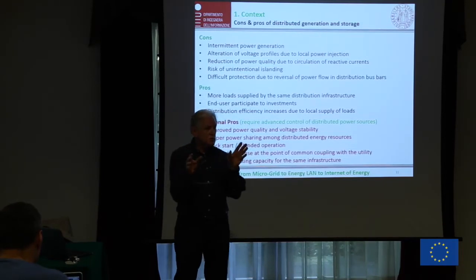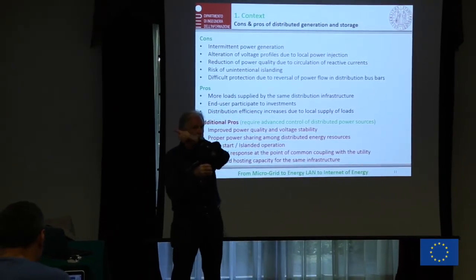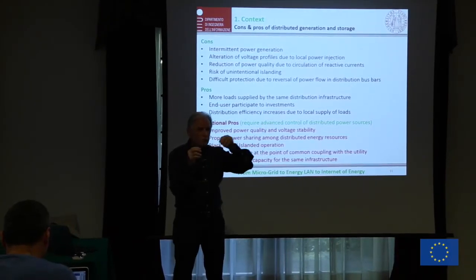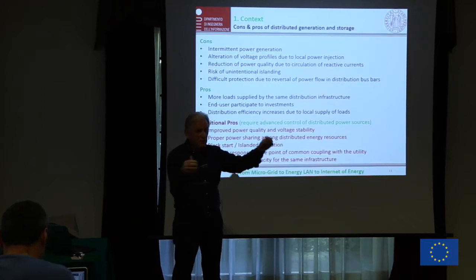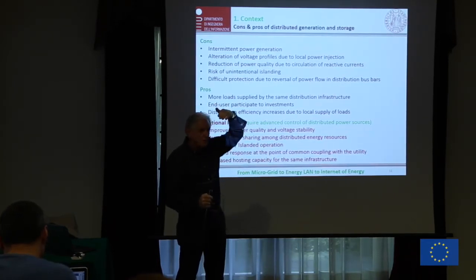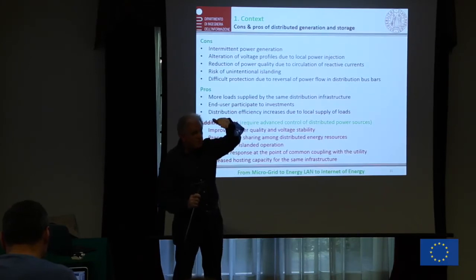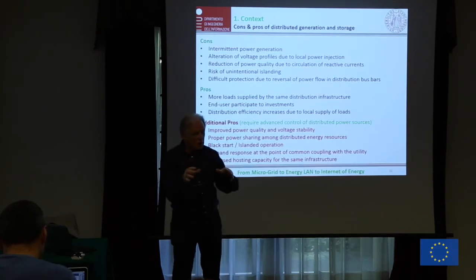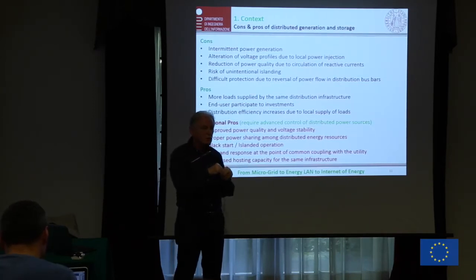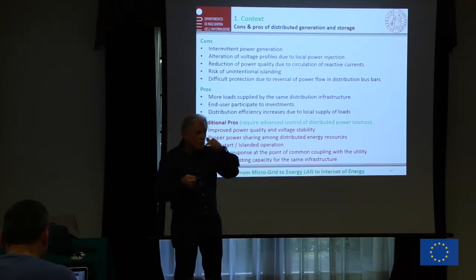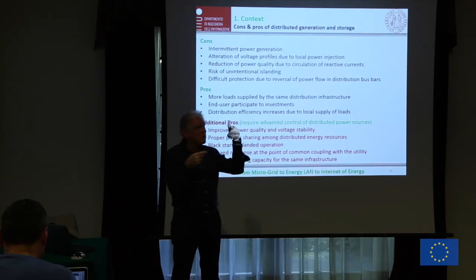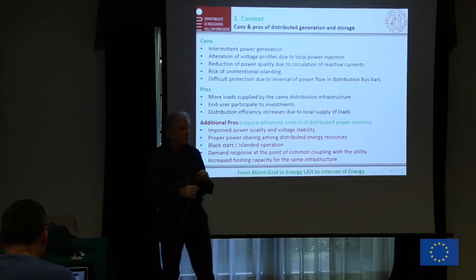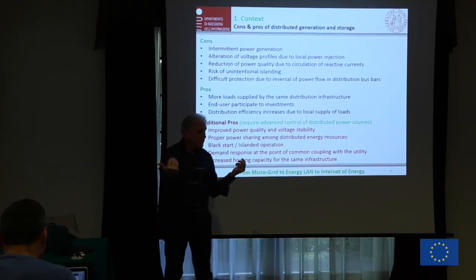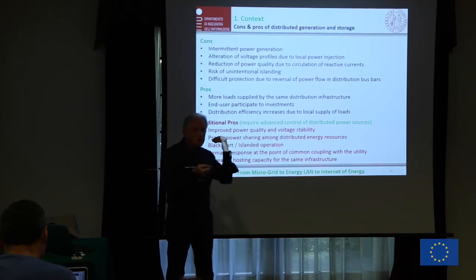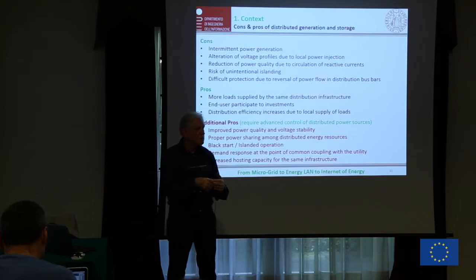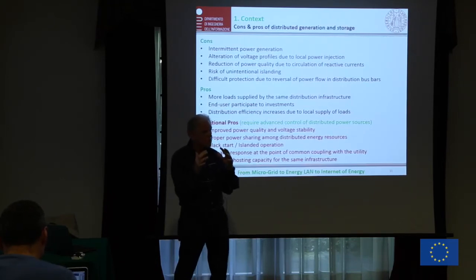The standard distribution systems rely on the fact that the power flows in one direction: it starts from the power station, crosses the transmission lines, goes down to the medium voltage distribution lines, and at the end to the low voltage distribution lines and the final user. You exactly know at each point of the system which is the direction of power flow. This is essential for allowing protection of the system, because if you open a switch upstream, everything downstream remains isolated. This is the basic mechanism of protection of electrical grids.